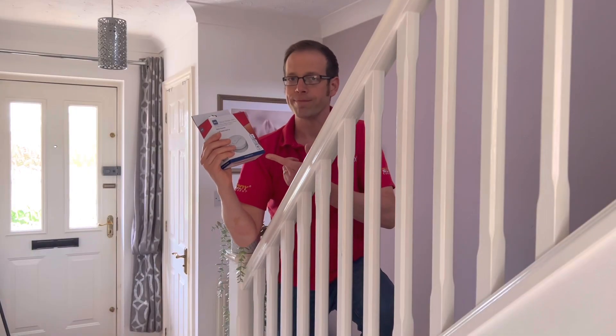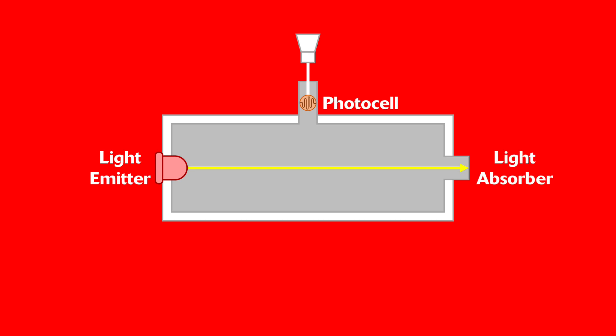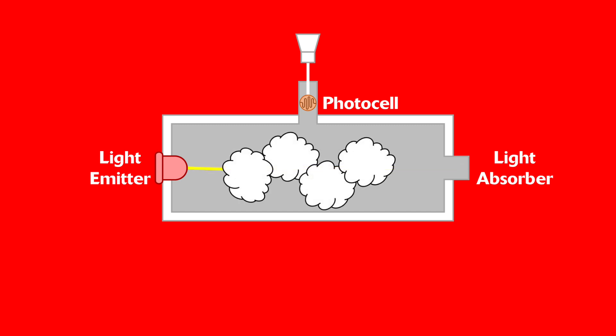So how do optical detectors work? Inside the detector there's a small chamber with a light source on one side, and a photocell sitting off to another side at an angle to the light source. Under normal operating conditions with no smoke, the light hits the far side of the chamber, is absorbed, and the photocell isn't triggered. If large particles of smoke from a smouldering fire enter the chamber, the light bounces off the smoke particles, hits the photocell, which is activated and triggers the alarm.